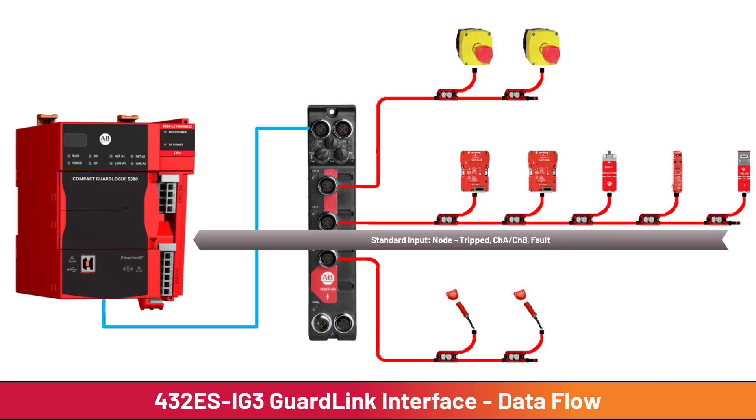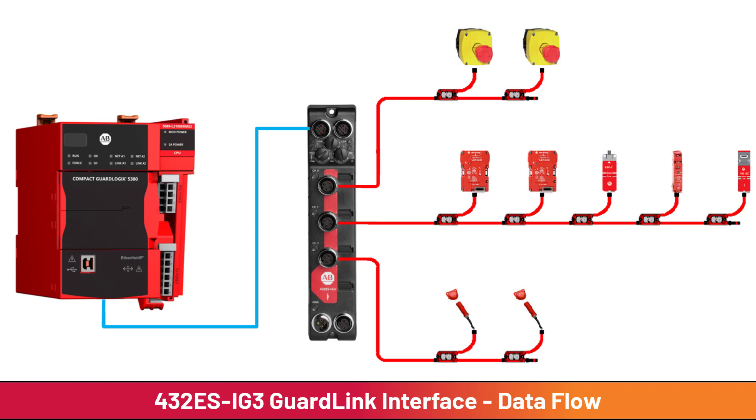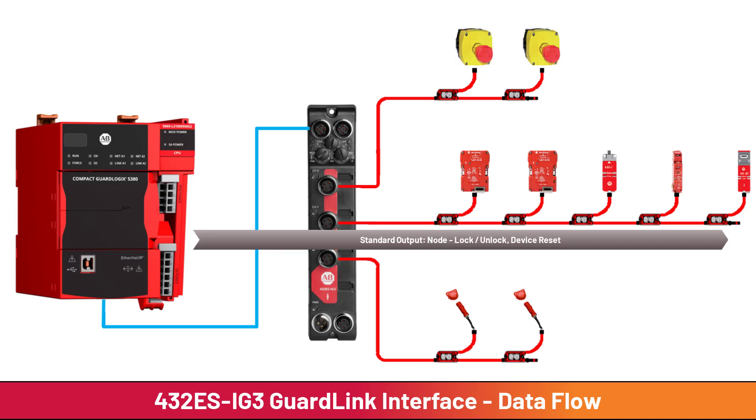The third type of data is standard output data to the GuardLink nodes. Standard output data includes guard door lock and unlock signals as well as device reset. Since the guard door lock control is coming from the standard control logic, there is no safety rating on the 432ESIG3 lock control.